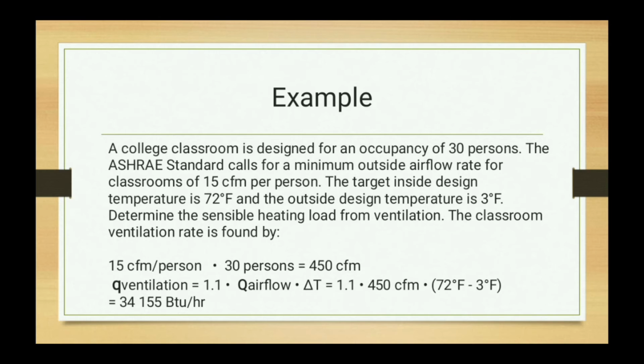So, halimbawa, for example, a college classroom is designed for an occupancy of 30. So, yung may isang classroom daw na design na ang kasyang katao o person ay 30. So, the ASHRAE standard calls for a minimum outside airflow rate for the classroom of 15 cubic feet per minute per person. The target inside design temperature is 72 degrees Fahrenheit and the outside design temperature is 3 degrees Fahrenheit. So determine the sensible heating load from ventilation. The classroom ventilation rate is found by, ito nga, 15 cubic feet per minute per person multiplied by 30 persons, which is equal to 450 cubic feet per minute. So, ito yung airflow niya.